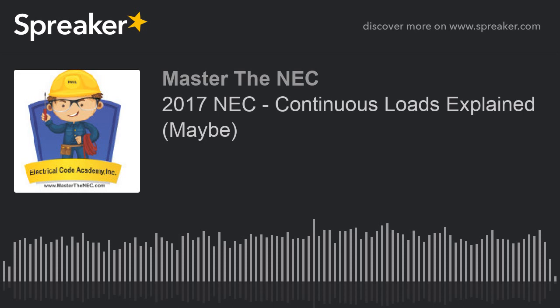In our case, like I said, if the 16 amps was a continuous load, that's the maximum load that can be on the 20 amp breaker, unless that breaker was actually rated at 100% for continuous load and non-continuous load. And that's a specialized breaker. Most of the breakers, for example, are limited to 80% due to the manufacturer's limitations. Okay, so that's kind of walking you through conductors and sizing.